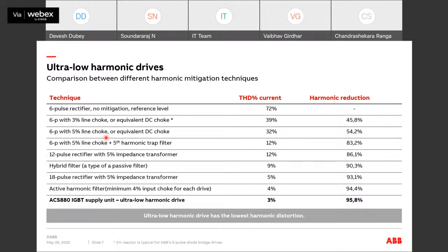We can bring it to 12% when we have a 12-pulse rectifier with 5% impedance, meaning three-winding transformers. Then if you increase the number of pulses further, it can come down to 5%. You can add a passive filter also, which will have a THD value of 9%. But the best solution, what I am suggesting for the industry, is an IGBT supply unit or a low harmonic drive, which can bring down the total harmonic distortion to 3%. So you can see the harmonic reduction happening in various technologies. The best is 95.8%, which is there with the IGBT supply unit.